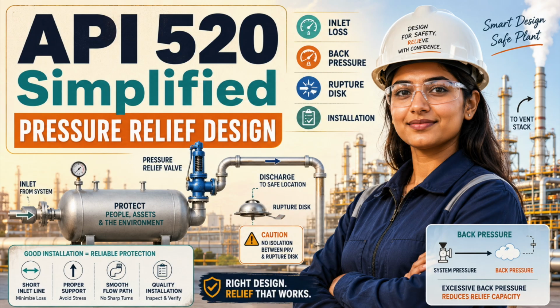A vessel containing liquid may relieve vapor. A heat exchanger may relieve liquid, vapor, or two-phase fluid depending on the failure mechanism. The correct question is not, what does the equipment normally contain? The correct question is, what reaches the relief device during the governing event?